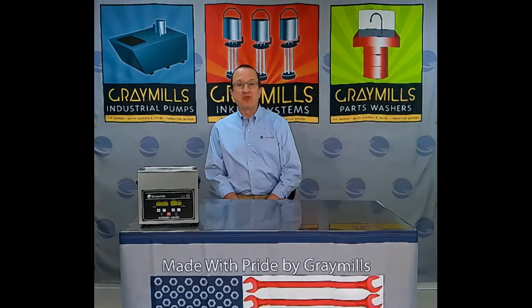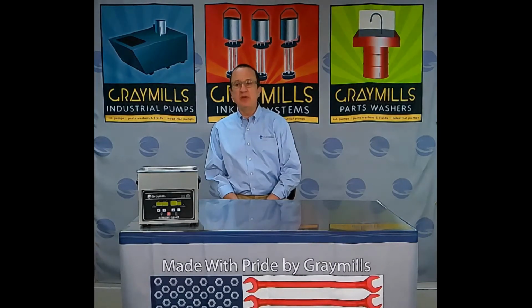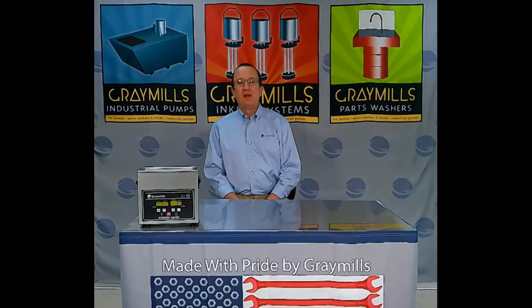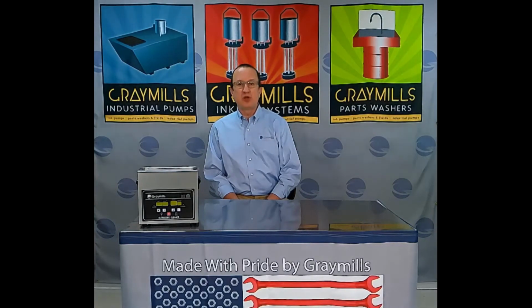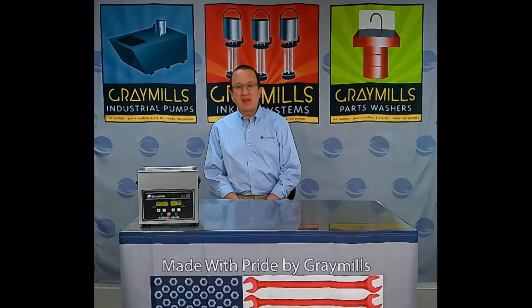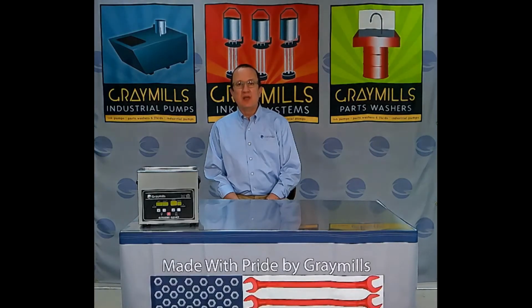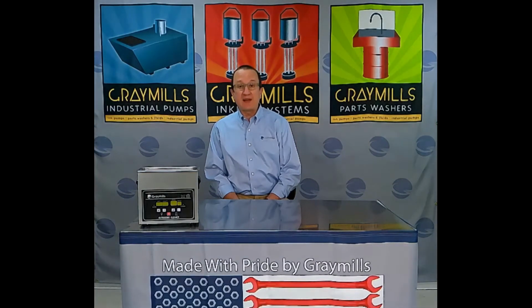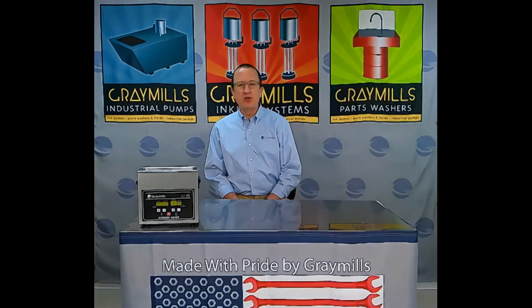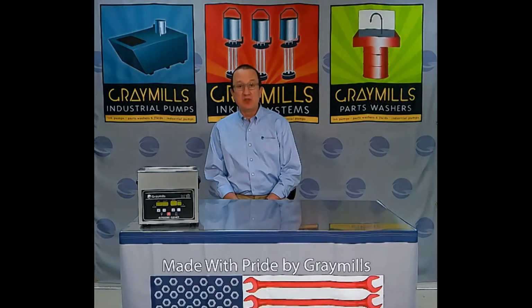Let's talk about chemistries. What kind of chemistries can you use in an ultrasonic tank? Typically it's a good water-based detergent. While the ultrasonic itself provides the cleaning action, you still want a wetting agent or surfactant to help remove the contaminants from the surface of the part. These tanks are usually heated too, so a typical temperature anywhere from 100 to 130 degrees is common. Keep in mind, these tanks will heat up as you're cleaning just from the energy of the ultrasonics themselves.